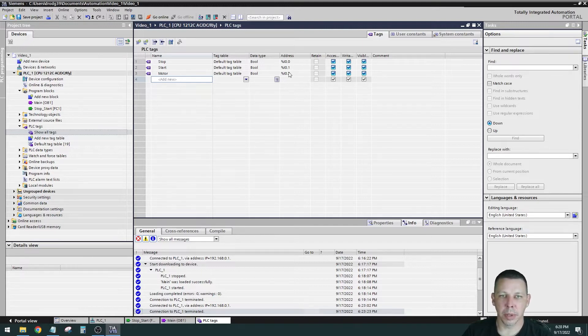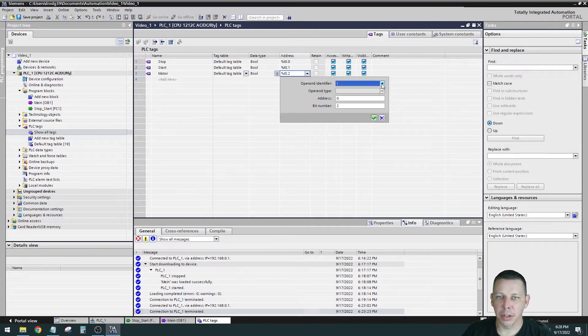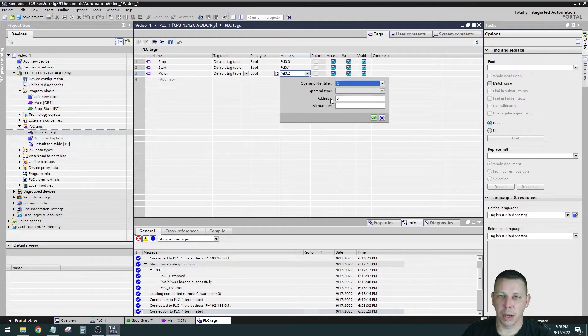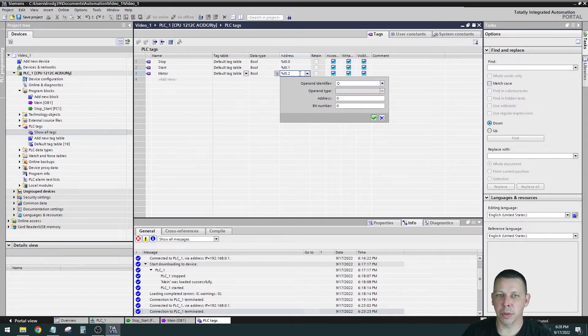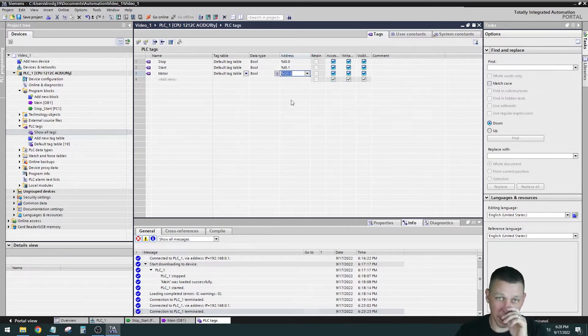My Stop is going to be input I0.0, my Start is input I0.1. My Motor is going to be an output — ignore the percent symbol. So it's I0.0: input byte zero, bit zero. You want to click on the Motor tag and change it from an input. Here's your identifier where you can make it an input, output, or memory bit. Q is outputs on Siemens. Select Q and set the address to byte zero, bit zero. I'd have to double-check the book on exactly what that first number represents — it might be a byte or 16-bit word.